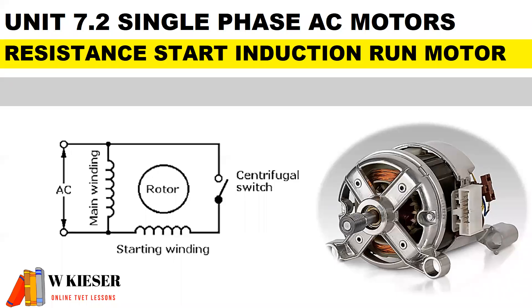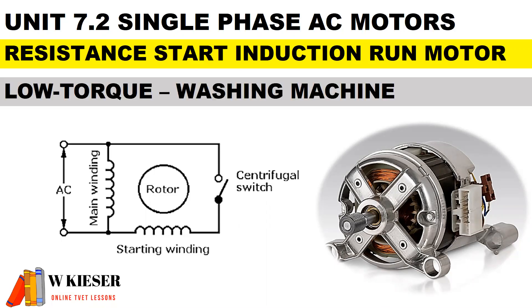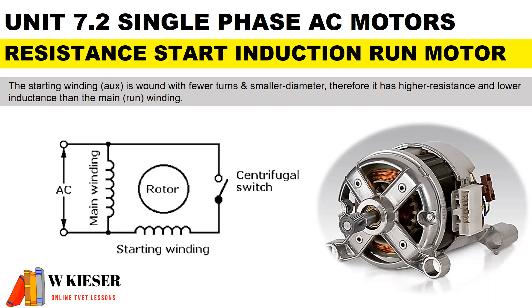We'll be looking at three types of single-phase AC motors, and the first one is the resistance start induction run motor. It has low torque, and a good application is a washing machine. The start winding, also known as the auxiliary winding, is wound with fewer turns and has a smaller diameter. Therefore, it has higher resistance and lower inductance than the main winding, also known as the run winding.